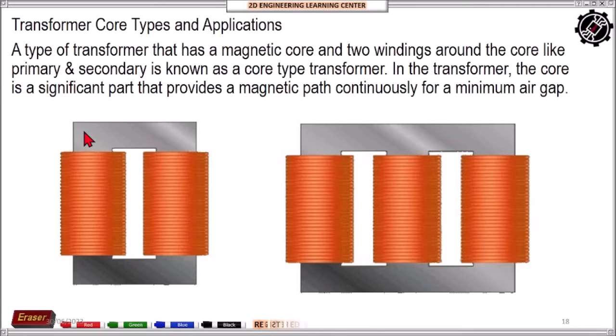Because of that, our transformer becomes hotter since the iron and copper losses are higher. So the coolants used in a transformer are the following: first we have the dry type transformer. When we say dry type, we don't add any liquid. It is self-cooled, with cooling obtained by natural circulation of air, or forced air cooled, with cooling obtained by forced circulation of air, sometimes referred to as fan cooled, where we attach a fan to the transformer. Fan cooling can increase transformer kVA rating by 25 to 50%, depending on the type and size of the transformer.